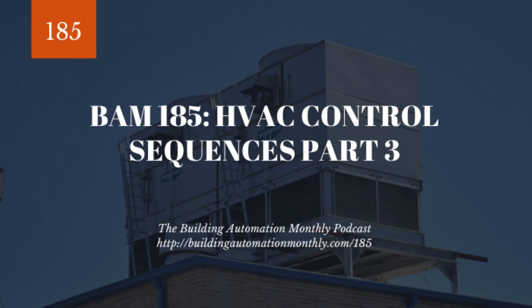The problem is when we introduce 90% relative humidity at hot temperatures, that is a ton of moisture that has to be removed by the system. And the only way the air handling system can remove moisture is to bring the temperature to saturation, which basically means that we cool the temperature down to the point where, as temperature lowers, it has less capability of holding moisture. So as the temperature gets lower, the moisture is going to condense and leave the airstream. It has to, because it can simply no longer be held and contained by that air at a colder temperature.